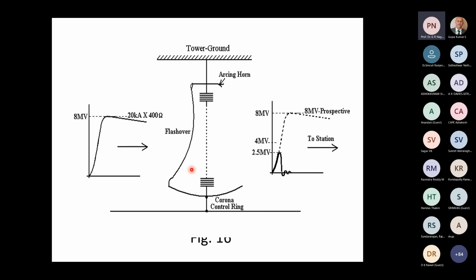Now, to take a simple example, I have assumed that the voltage appearing from this end is 8 megavolts. We have seen these values are possible because 20 kiloamperes multiplied by 400 ohm surge impedance gives us 8 megavolts here. 8 megavolts is represented by this wave shape. Now it flashes over, typically flashes over around 2.5 megavolts for a certain transmission line voltage. For example, if you take a 220 kV line, 2.5 megavolts is a little too on the higher side. If it's a 400 kV line, 2.5 megavolts is acceptable. We'll see why.